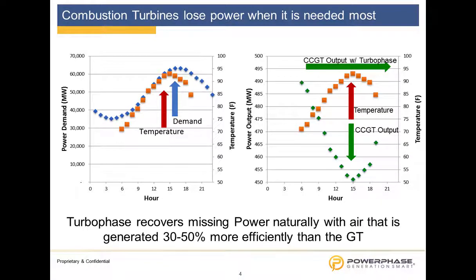Where that addresses the need is this very simple slide. I know it is oversimplified, but as we all know, your gas turbine is a fixed volume mass density machine. What I mean by that is as it gets hotter, the density of the air goes down, and your power goes down proportionally, almost linearly. Nobody runs a gas turbine year-round on an ISO day, 15C, 60% relative humidity, and sea level. I challenge anyone to find a power plant located at those specs, but those are the design specs. So when we apply Turbophase to the gas turbine, we're replacing that air with additional compressed air to generate more power out of the gas turbine and to improve the efficiency of the underlying gas turbine asset.